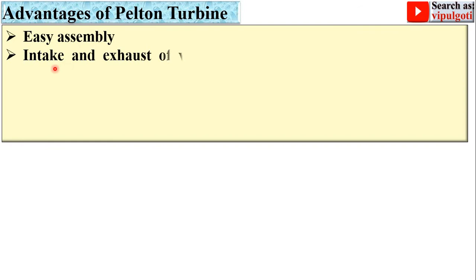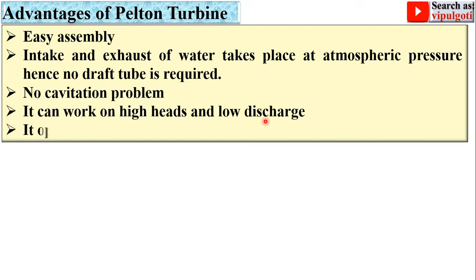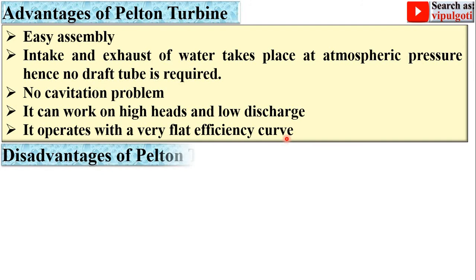Next: advantages of the Pelton turbine. Easy assembly. Intake and exhaust of water takes place at atmospheric pressure, so no draft tube is required. There is no cavitation problem in impulse turbines. It can work on high heads and low discharge. It operates with a very flat efficiency curve.